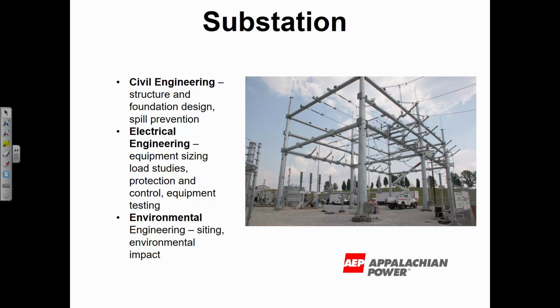So what kind of engineers would we use for this type of work? Again, civil engineering for structure, foundation design, spill prevention. That's a substation class transformer. Anytime we have one of those, they're filled with oil, so we've got to do spill prevention dikes. We want to contain every drop of oil in case that transformer would break down and fail.